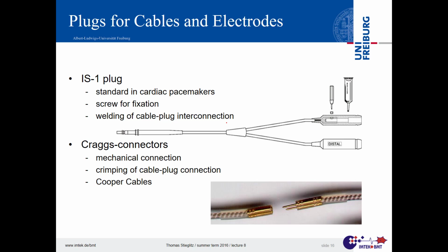Craggs-connectors have been an alternative at points in time from the mid-70s on, where the cardiac pacemaker cable still had one contact. It was not that much, and Craggs-connectors came with 3 of them. So helically wound cables with 3 independent lines that go in 3 pins, and they were smaller than the other things around. The company is still around. Fintech Medical in the UK, a very small company. Don't know if they have 3 or 5 employees or 10 or something like that, but really small, very customer design.